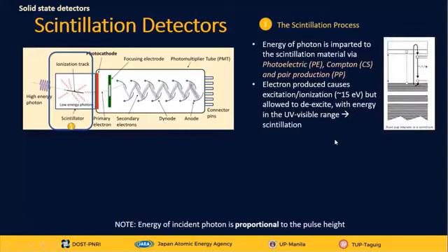So what happens here? When we allow the electrons to excite from the valence band to the conduction band, there's a possibility that the energy will be absorbed within the scintillation material. In the sodium iodide, for example, they use a thallium dopant, which adds an energy band that allows transition from the conduction band to this exciton band, and further de-excitation to the valence band, producing light, producing photons of lower energy. Thus, we can see this in the UV to visible range.